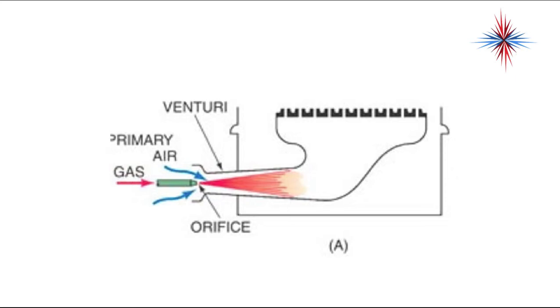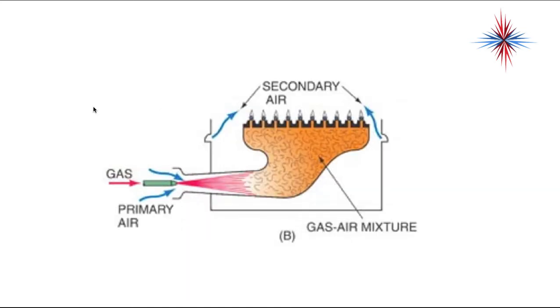When we look at the gas burner, we mix primary air into the gas as it comes out of the orifice, right here. We mix it together in an area called the venturi, and then push it up into the burner where it starts burning at the top. That's primary air. Secondary air is around the burner — we have the gas-air mixture in the burner and flames at the top, and secondary air surrounds the burner to help support the combustion process.